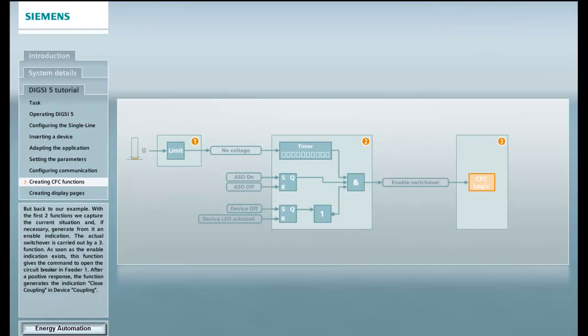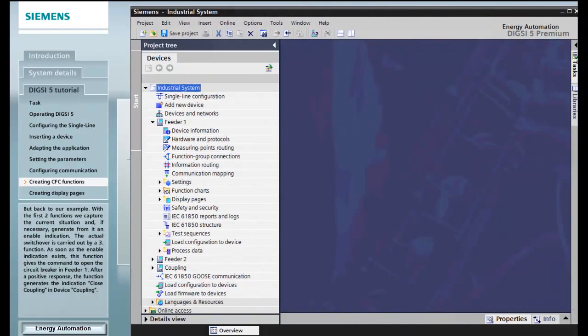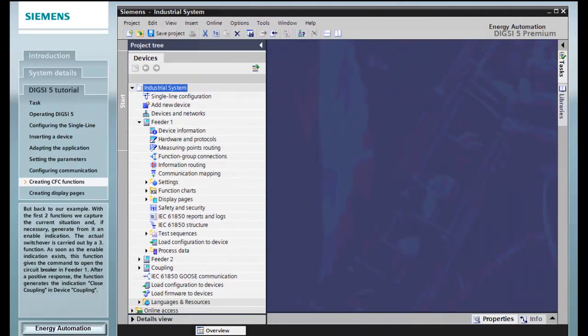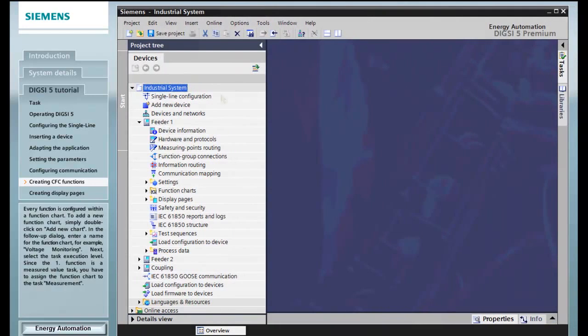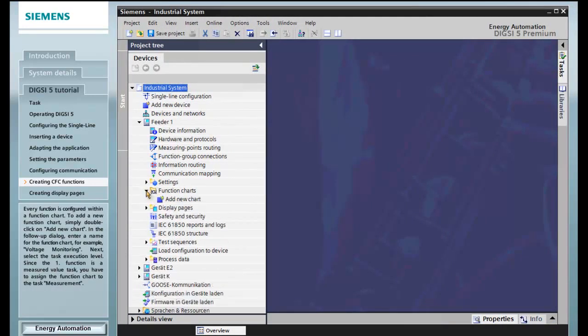The actual switchover is carried out by a third function. As soon as the enable indication exists, this function gives the command to open the circuit breaker in feeder 1. After a positive response, the function generates the indication close coupling in device coupling.